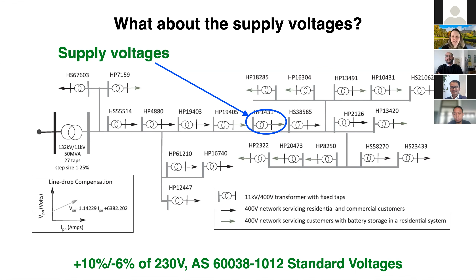To answer this, we'll look at the impact on supply voltages by zooming into the substation highlighted, specifically the customers connected to supply transformer HP1431. In the top figure, our baseline, we observe voltages when no batteries are installed along the feeder, noting 50% of customers along the feeder have connected solar PV. We observed that 23 out of the 37 customers connected to this distribution transformer have voltage excursions outside our allowable limits.